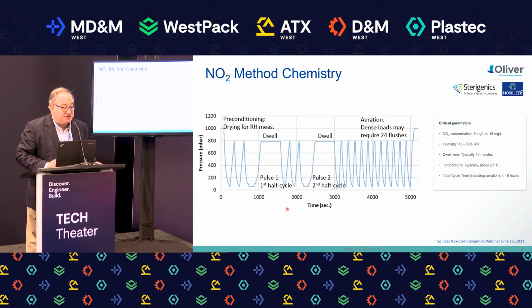Here's the next slide to show you a typical cycle for NO2. After we load the sterilizer with product, we do some preconditioning where we basically evacuate the chamber several times to condition the load. We then draw the vacuum on it and introduce humidity, where the pointer is right now. We introduce humidity to the load and then dose with NO2. At the peak of this curve is when we start administering the dwell. So typically we're at 1 times 10 to the minus 6 SAL in the fractional cycle at this point. We then repeat the vacuums and redo the introduction of humidity and NO2 to the process and repeat the dwell to make the full cycle.